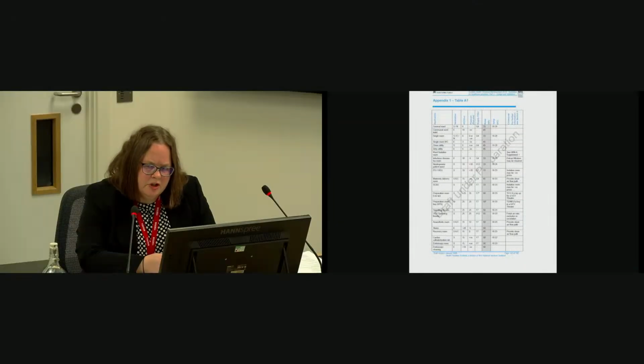Let's again look at this. If the definition, we'll come back to the definition in a moment, is for the whole ward, how would you achieve these requirements for a whole ward? What would that physically involve? In terms of refurbishment, do you mean? Well, in terms of, would it have to have a lobby at the entrance to the ward? If you're going to achieve 10 air changes and 10 Pascal positive pressure on a ward, would you have to have a lobby at the entrance to the ward? I'm not convinced a lobby would be essential if you were achieving HEPA filtration in a corridor and a positive pressure of 10 pascals and air changes of 10.